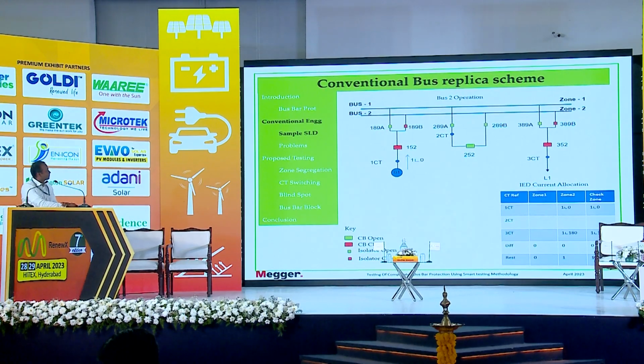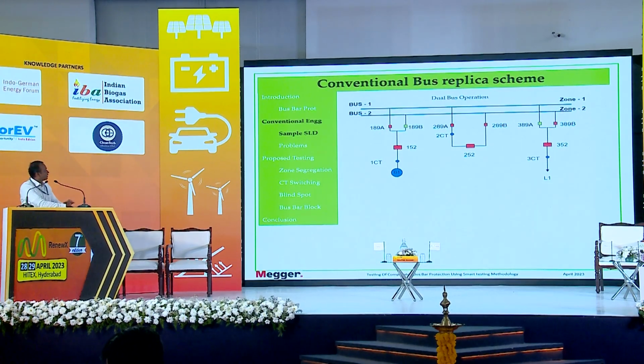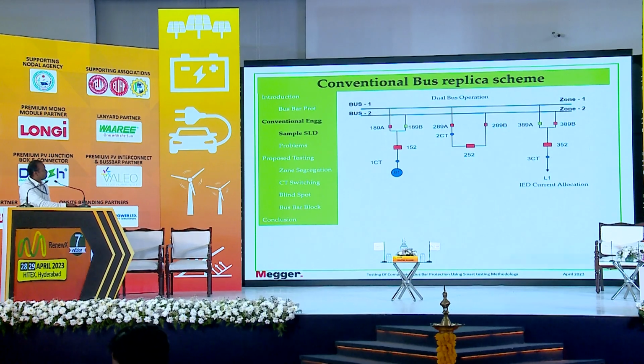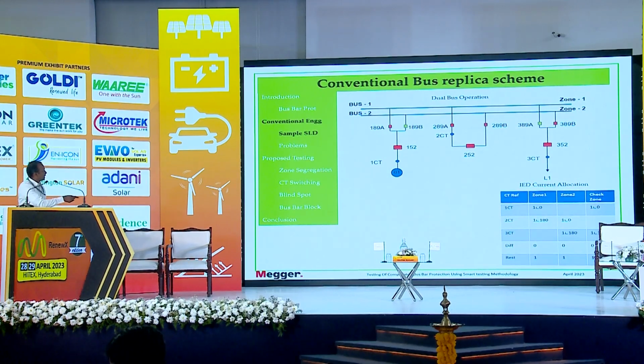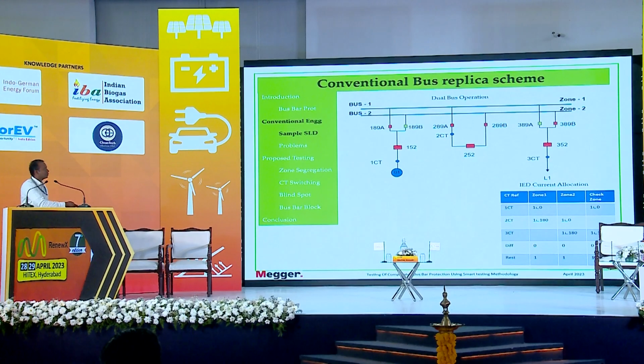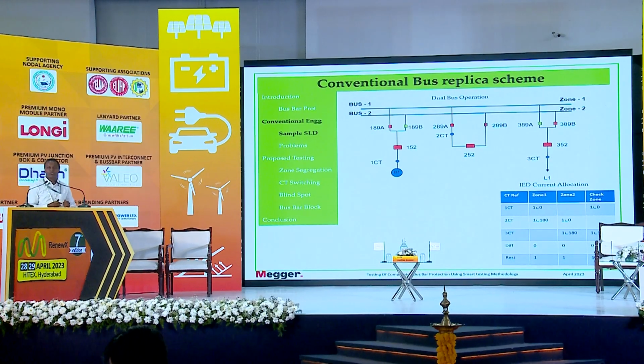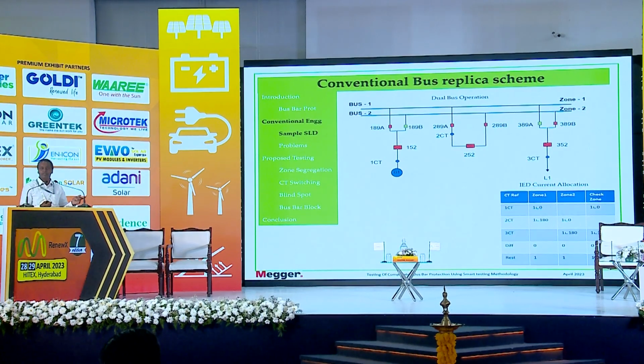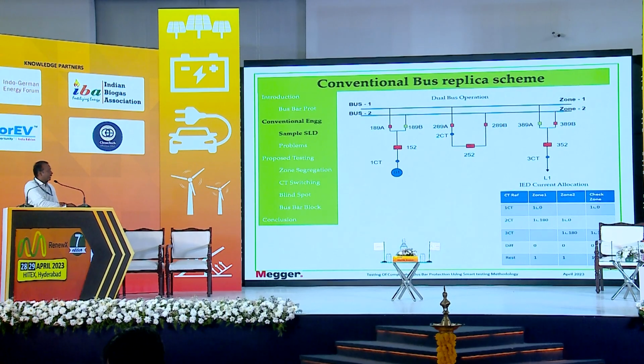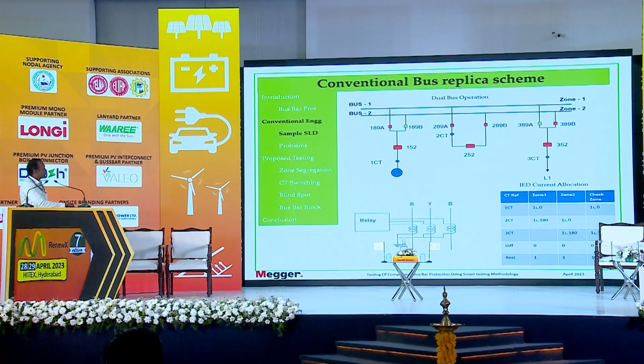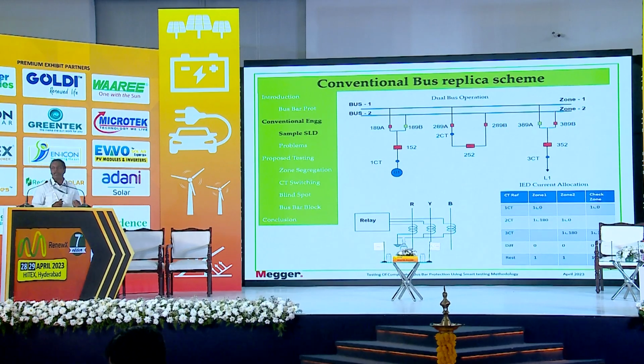The third type of operation, we can feed in this manner. So the solar connects to bus 1, we have a bus coupler, and from bus 2 it is feeding. So what happens here is, 1 CT is read in zone 1, 3 CT is read in zone 2, and the bus coupler is actually read in both zones because it is sending the current out from bus 1 and sending the current inside bus 2. So since the current is actually entering one bus and leaving the other bus, the angle also has to be taken respectively. So we can see here 1 angle 0 plus 1 angle 180, still the system is actually perfect. And this is how the angle 1 angle 0 and 180 varies for 2 CT, that is based on the star point connectivity of the CT.